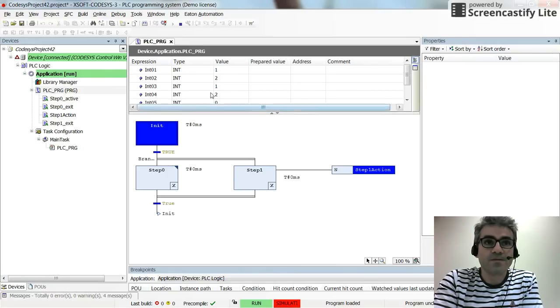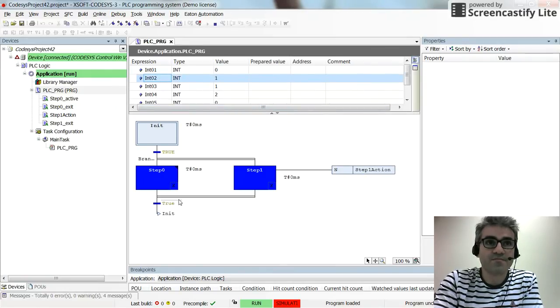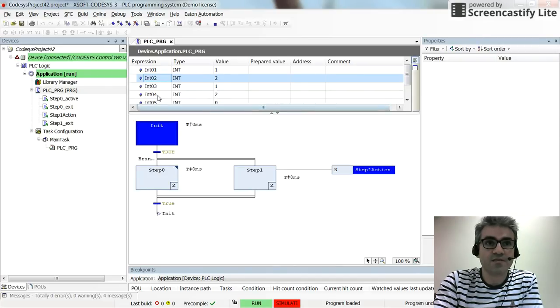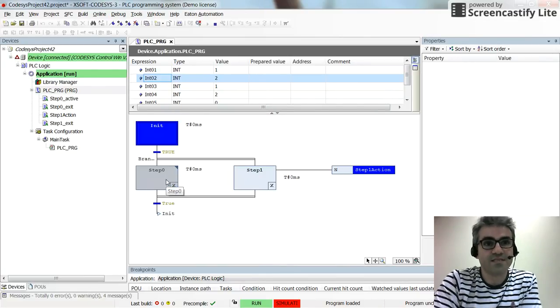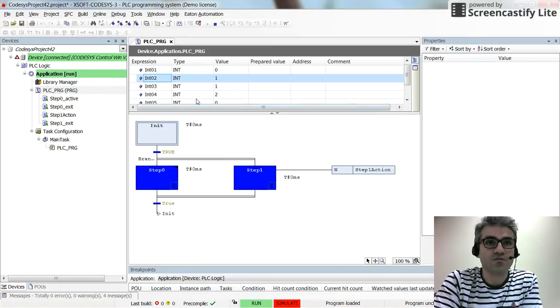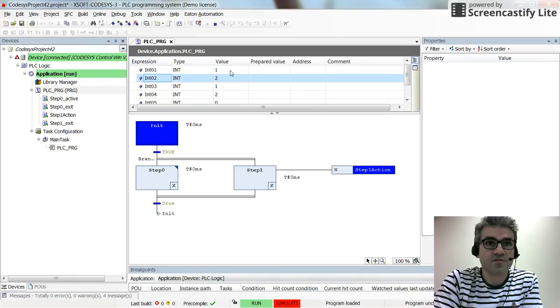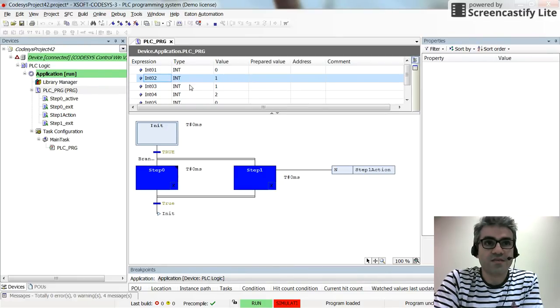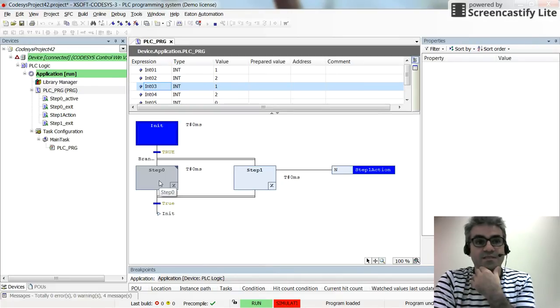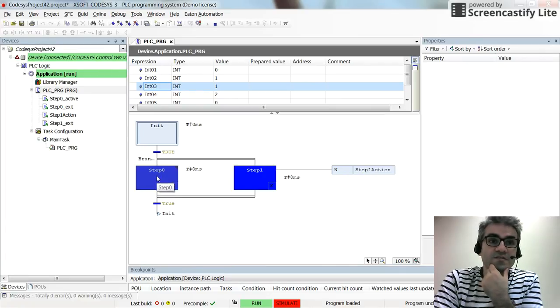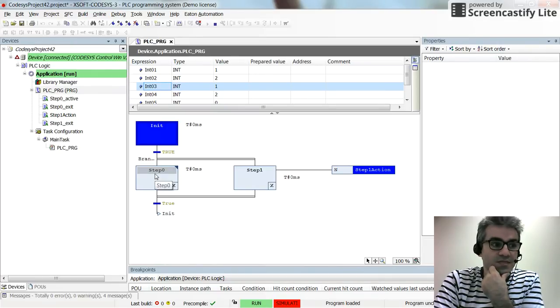Having a look at the variables: int02 keeps track of the value that comes from Step 0, and int04 keeps track of the value which comes from Step 1. In Step 0, as the step active action, we are adding 1 to the value of int01, which is reset to 0 each time. So int01 will have values of 0 and 1 — and the value for int03 is always 1. This means the step active action in Step 0 is executed only once.